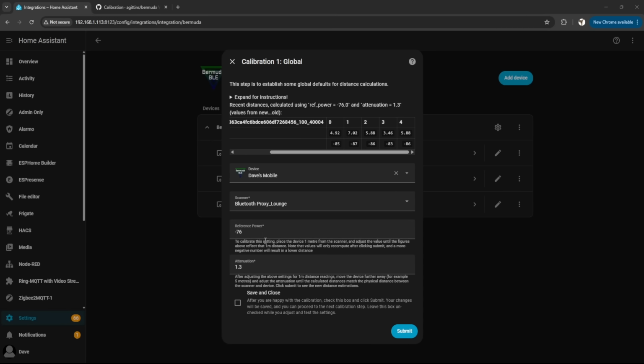Okay, I went back a few steps and I changed the reference power from -80 to -76. Then I set the attenuation value to 1.3 and it seems to be a little bit better. I'm just going to move the device so it's back to 1 meter and just confirm that value at 1 meter is what I want it to be showing. Now the device is back to being 1 meter away from the scanner, so I'm going to hit submit and hope for the best it's behaving itself.